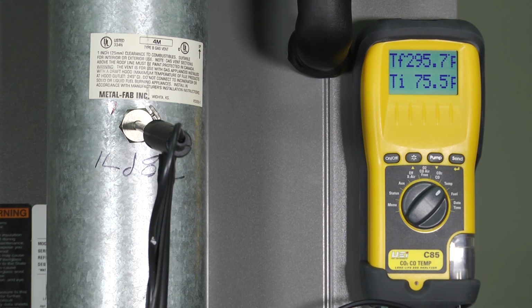The great thing about a flue gas analyzer is it tells me so many things in this market. We all have those installers that screw our gas piping in with a 2-foot pipe wrench and start tightening that gas piping and don't use a backup wrench. The downside to that is we can actually kick our burners out a bit so they're not burning down the center of our heat exchanger the proper way.